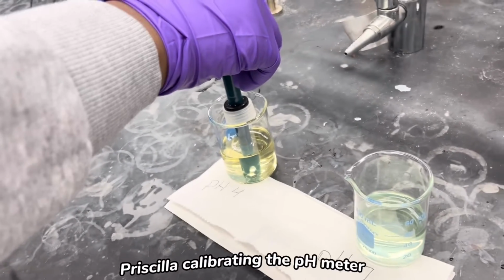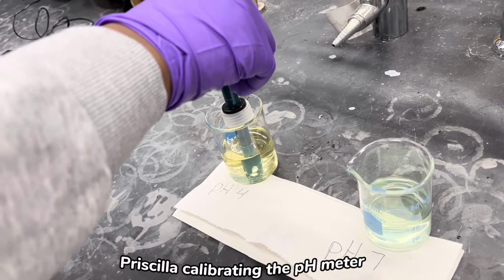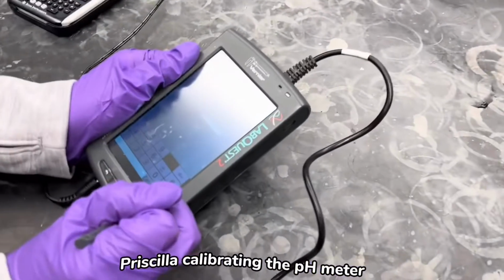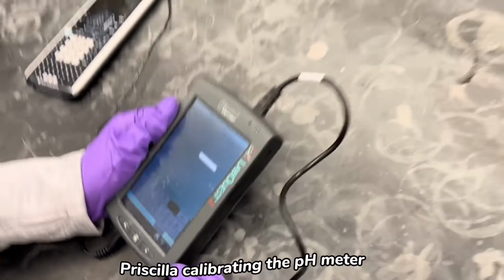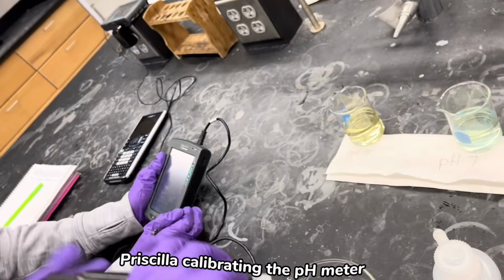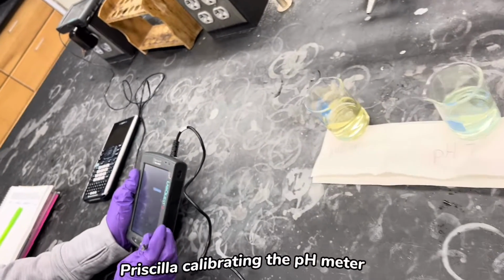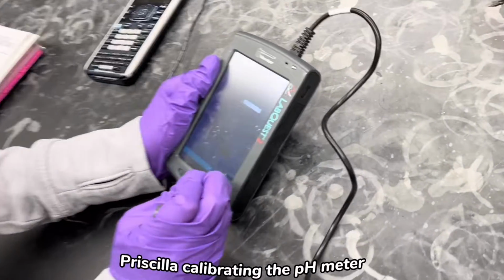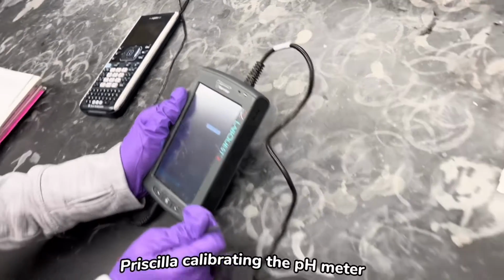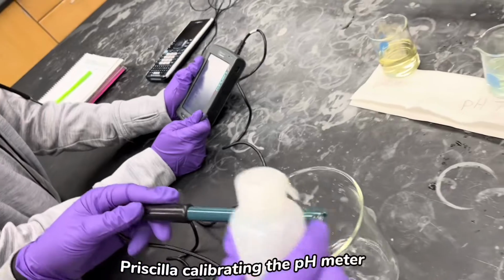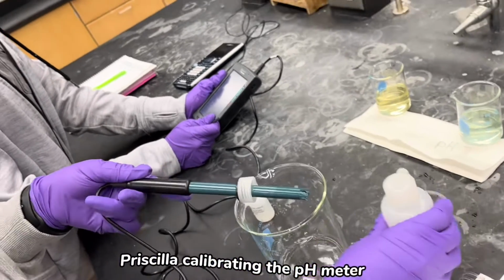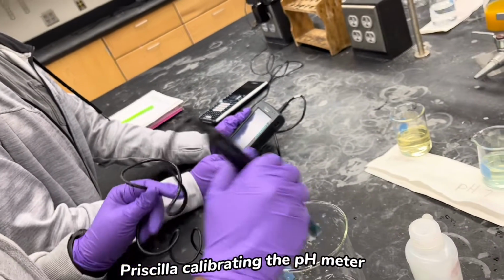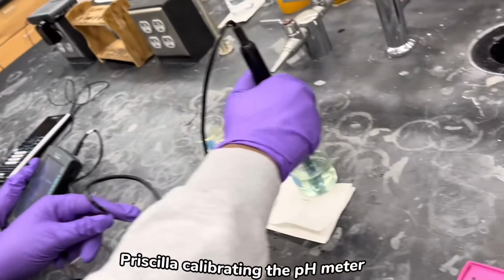Then we rinse off the pH probe before placing it in buffer 7, and we place the pH probe in buffer 7 until it reaches a stable voltage. Then we enter pH 7. Then we rinse it off. A thing to keep in mind is in between every use, you have to rinse off the pH probe to accurately read the pH substance.